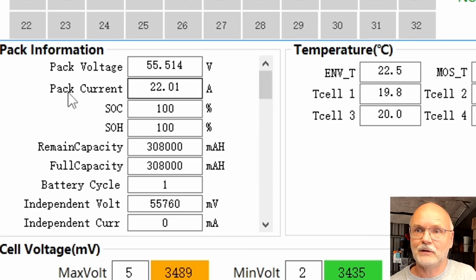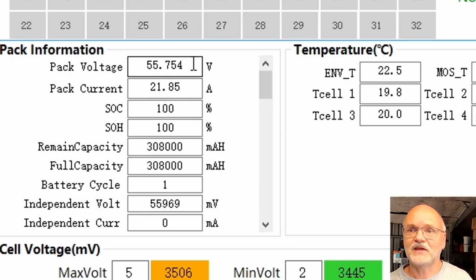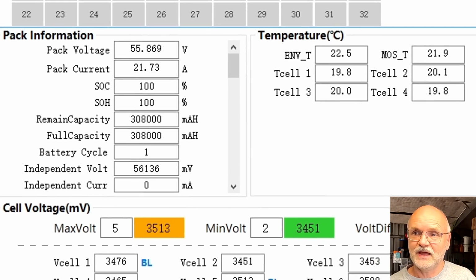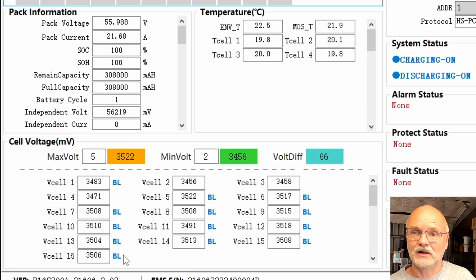We can see the current is ramping up to 21 amps, 55.7 we have. So we're charging to 57 volts now, and we watch the deviation here, to see if one of the cells actually hits 3.65 volts. Deviation is going up - 56.6. Oh, which one comes first?